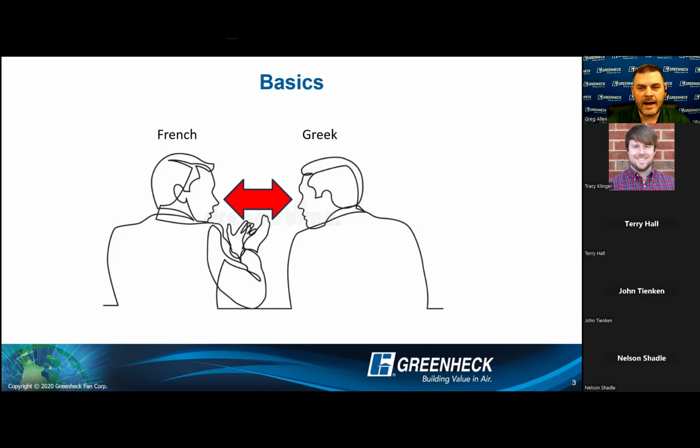One of the things I come across, I assist our customer service teams when there's a trouble call. And sometimes what I'm running across is device A won't work with fan B. And it's like, well, are we saying the right things? Are we communicating the right way? This is really easy to miss. But if you have some of the key lingo, we can start tightening up designs, sequence of operations, specs, drawings, fan schedules, if you have some of the verbiage to throw on it.